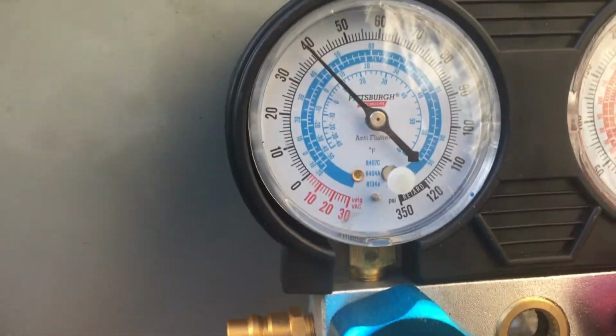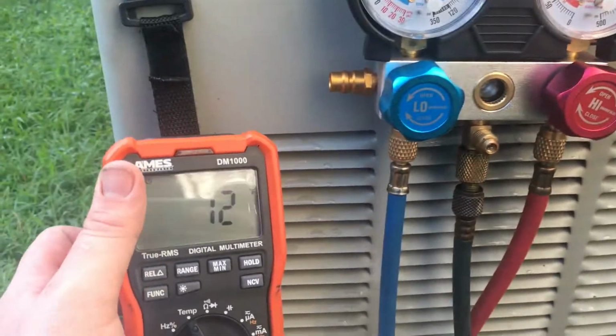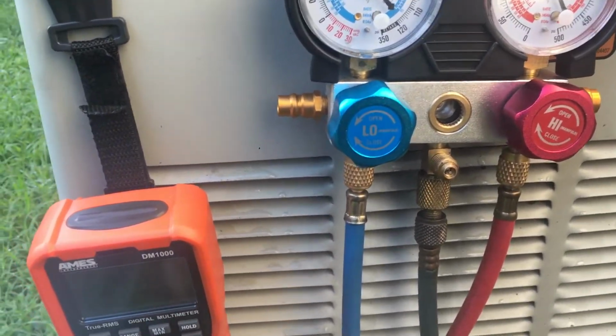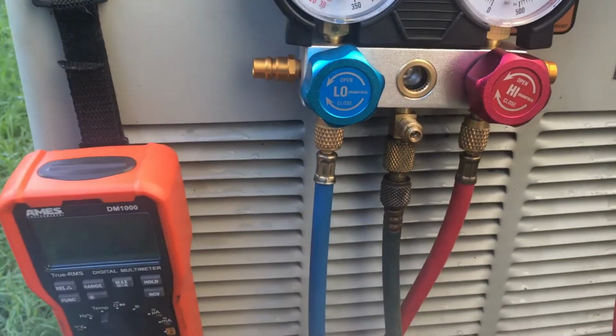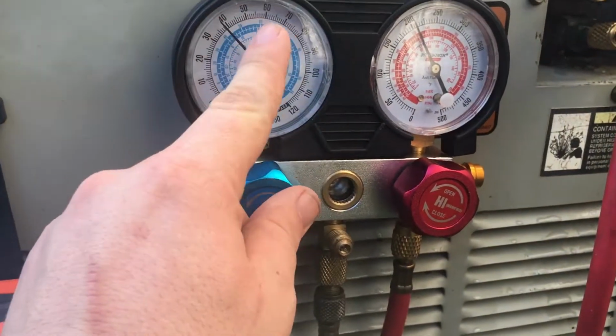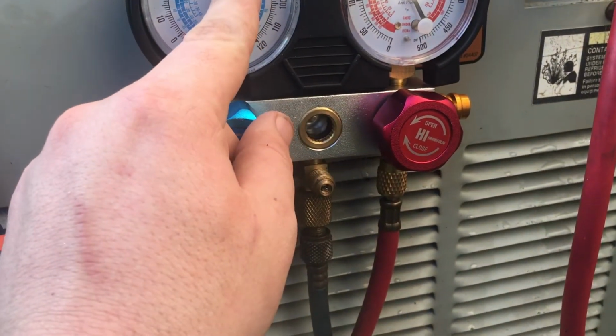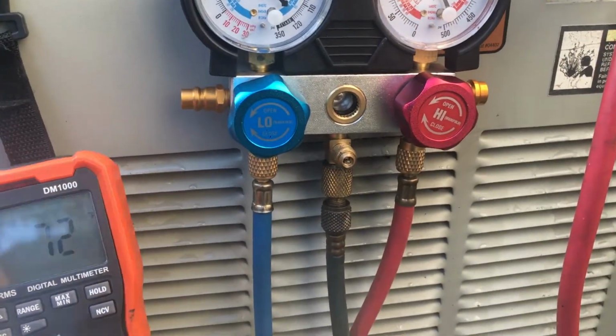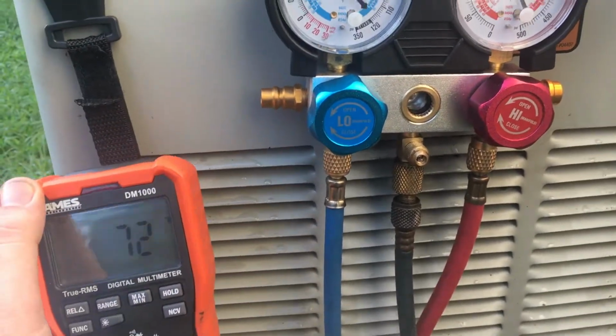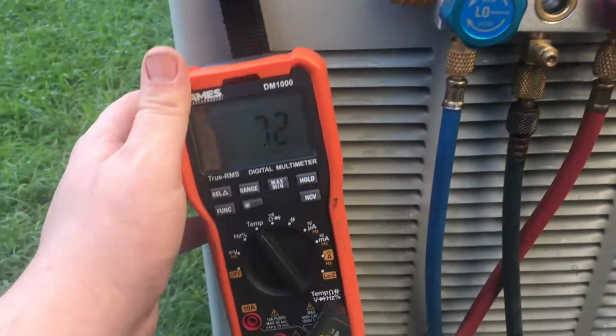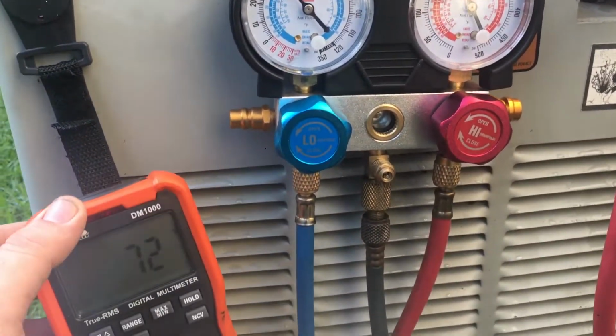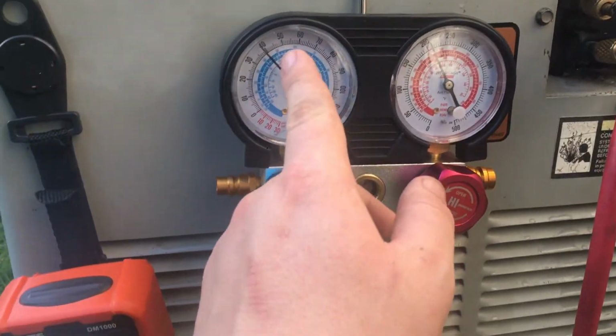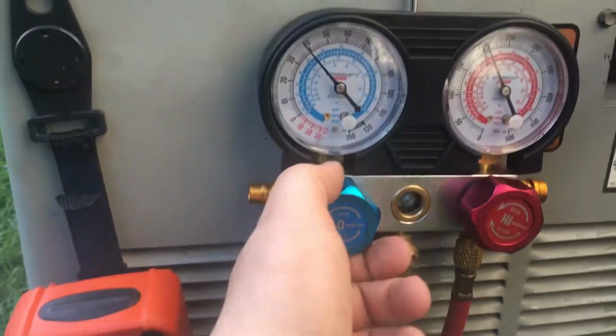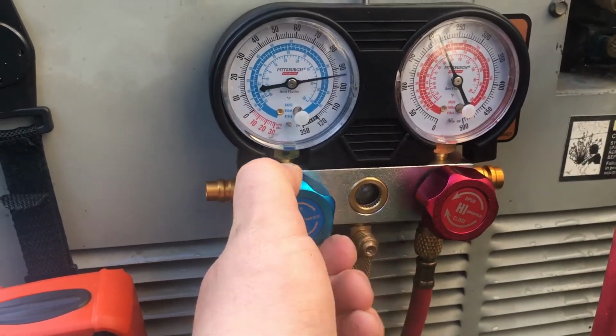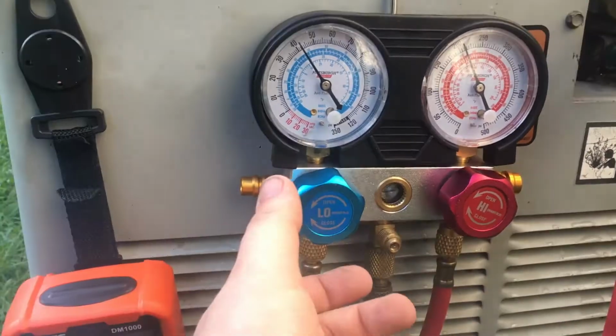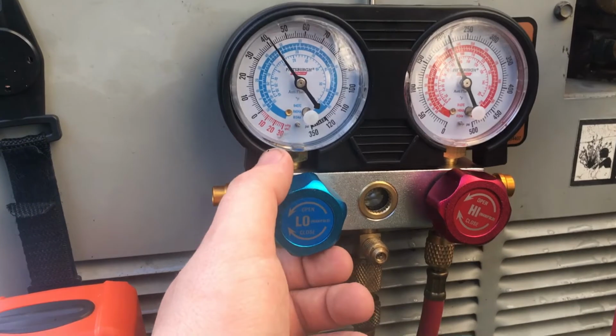We're at about 8 degrees saturated temp versus 72 on the suction line. So we're still at about 64 degrees of superheat. It should probably be around here somewhere. See, that'd be 30. Our target superheat, I'm not quite sure, because I actually have the superheat app this time, not the chart, and the app won't let me calculate target superheat until I get it up enough to a certain point. I'll add some until I get that superheat up enough to where the app will let me calculate it.